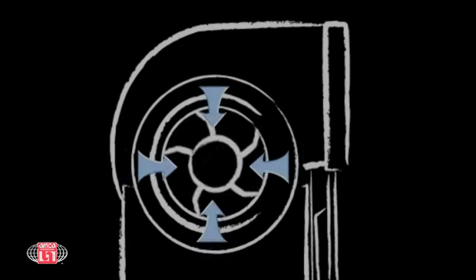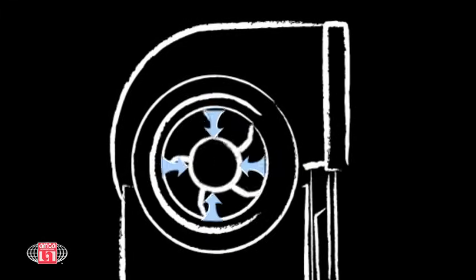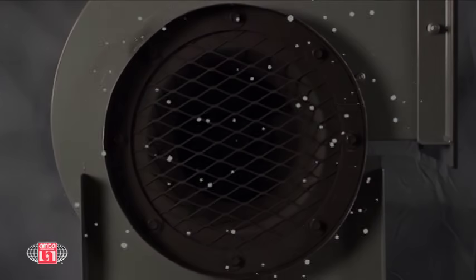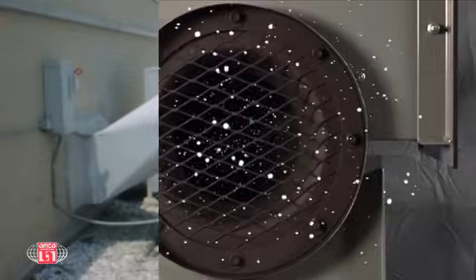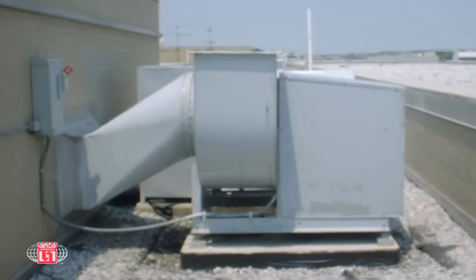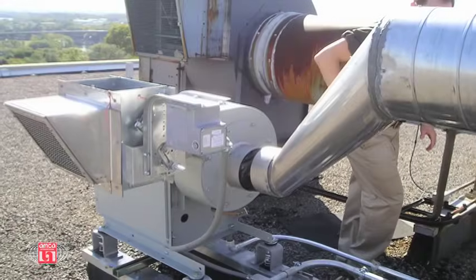System effect at the fan inlet and outlet seriously impacts air flow. The first major impact involves proper fan inlet design. As stated earlier, the air flow at the inlet must be fully developed, symmetrical, and free from swirl. Non-uniform inlet flow is the biggest cause of system loss. Factors adversely affecting inlet flow are insertion of obstructions, elbows and dampers too close to the fan inlet.